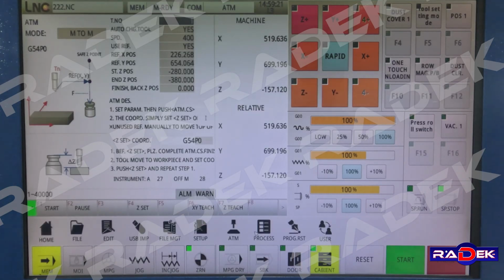It's important for the vacuum pumps to run before we set up the 0 position of the z-axis, because when the vacuum is engaged it will pull the workpiece downwards for a millimeter or more and fix its position on the working table. So we turn on the vacuum pumps by clicking the button VAC1 located in the right side of the interface, and then manually turn the physical vacuum pump switch in the running position.